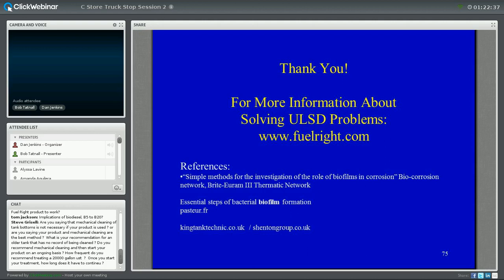Don't mess with water blasting, sand blasting. Shovel and scrape. Get the bulk of the solids out of there, bring them out, close it up, treat it, refill it, put it in service. There will be no downside. There won't be a ripple with that kind of a situation. But you can save a lot of money by just treating, even if you have to change a couple filters before things settle down.